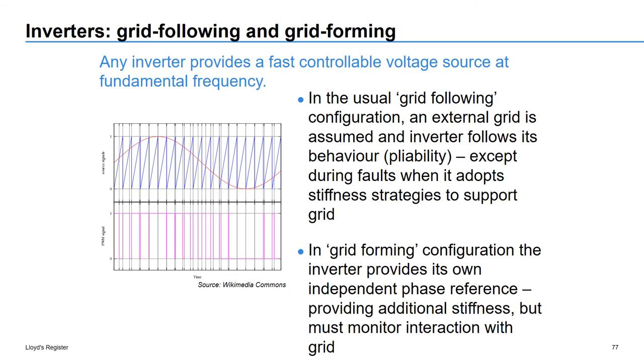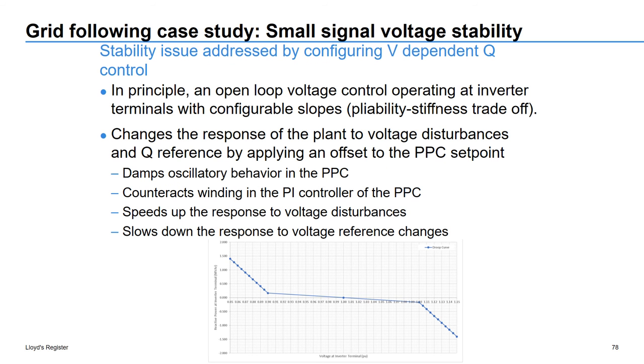The alternative grid forming configuration has been discussed by others and does more to mimic the voltage source behaviour of a machine. And in that case, the fault behaviour is closer to that Ohm's law behaviour that adapts to the characteristics of the faulted network. I'll mention now, by way of a case study, a grid following inverter example in the, actually it was the West Murray region, where, as is well known, we had issues with the weakness of the local grid.